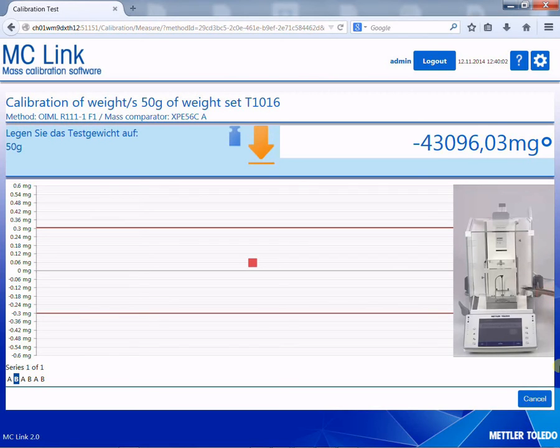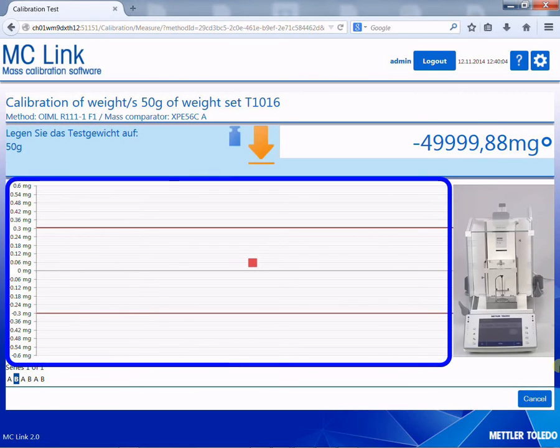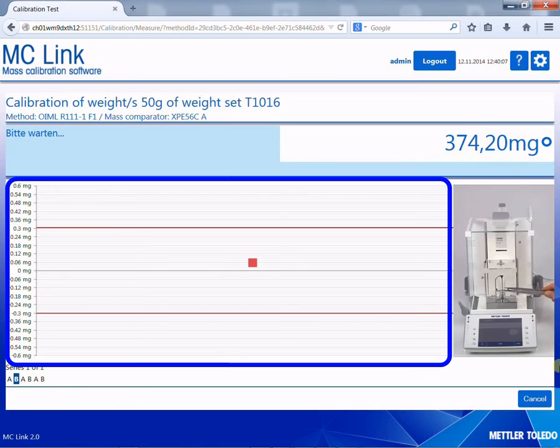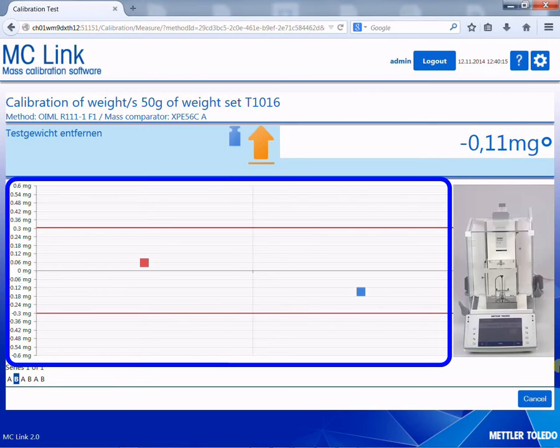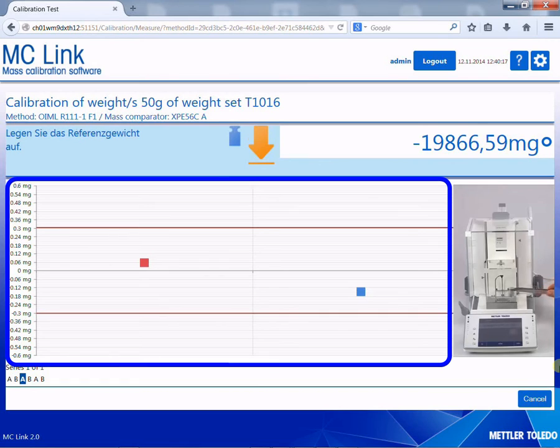During the calibration, you have full visual control of readings, tolerance limits, and actual uncertainties. With statistical testing — EN, F, T, and control chart tests — process quality is kept to the highest level.